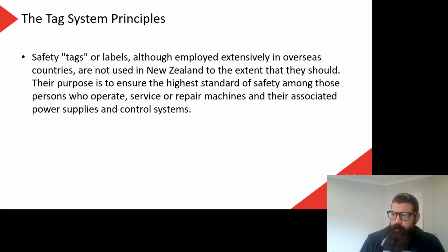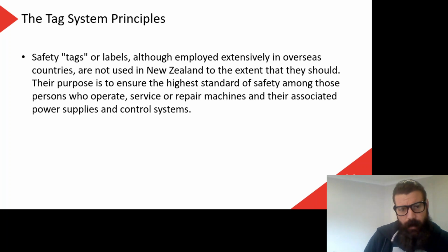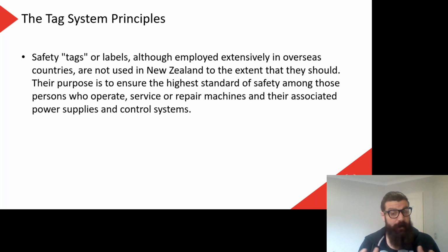And then the second one is that you may also need to isolate and lock out stuff that is not electrical. A good example of that is in my previous experience in the fuel industry. If we were doing work on the fuel part of a dispenser or anything on the site, we would do an electrical isolation for any motors and stuff like that, so they're not going to start and pump fuel. But at the same time, we would have valves on the fuel lines, and you would turn those off and lock them as well, because that prevents any fuel being pushed out through the line while you've got the line open, right? And you might see that in pneumatic systems with compressed air.